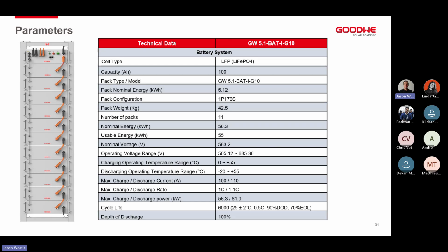The physical pack level is half the size of the previous BAT100, so it's 5.12 kilowatt hours per rack as opposed to 10.24, with each module weighing just over 42 kgs. That means it is possible for 2 people to install the battery rack themselves, unless you are strong enough to lift 42 kgs to shoulder height, then you can obviously do this alone. There are 11 packs in the total solution. We can lessen the packs down to 10. When we do, we get a usable energy of 50 kilowatt hours, and that is more suited to our 40 kilowatt unit as opposed to the 50 kilowatt inverter.